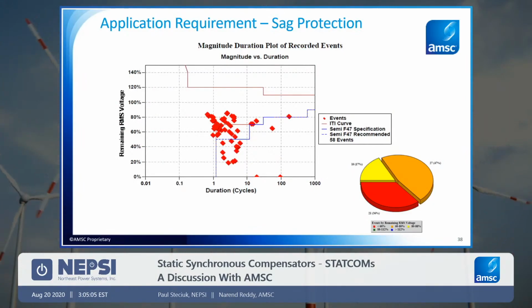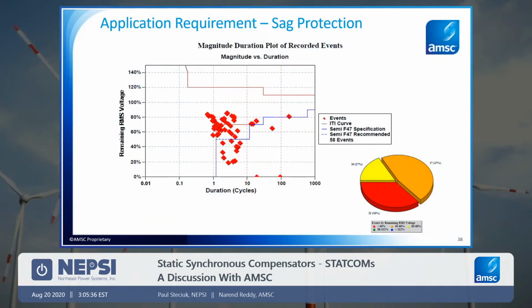And typically these tools or critical facilities go by some recommendations or sag thresholds that they should live with, such as the ITI curve or SEMI F47. This allows them some room in terms of ability to ride through some of these sags.